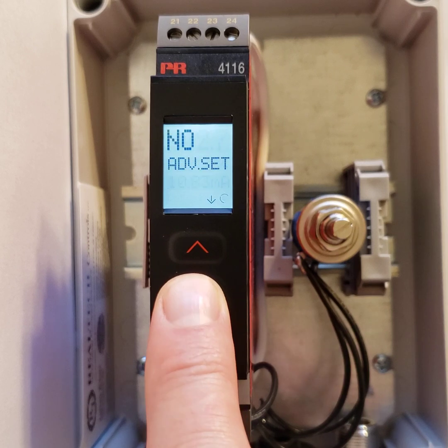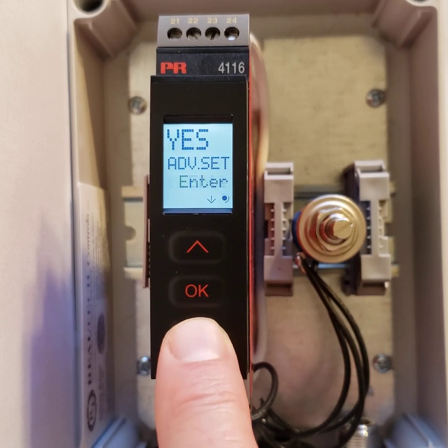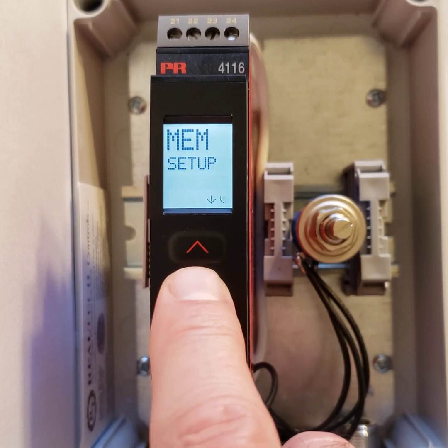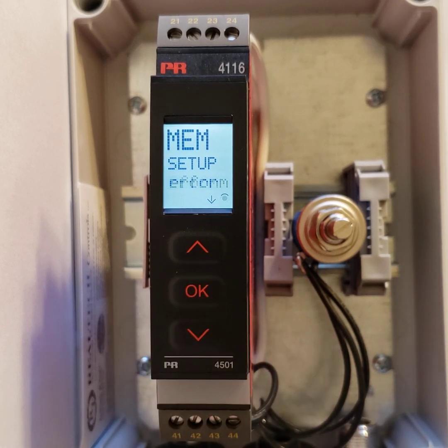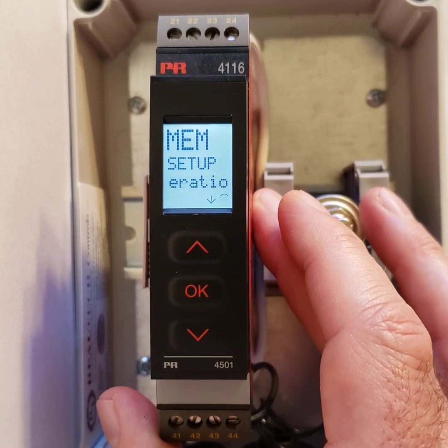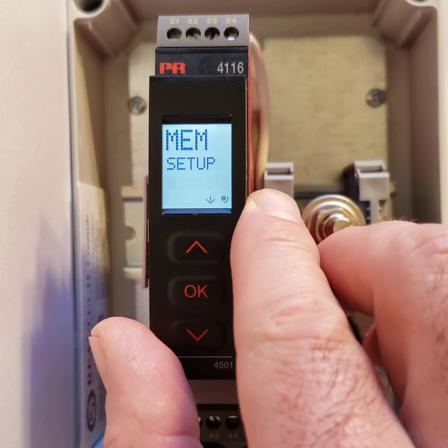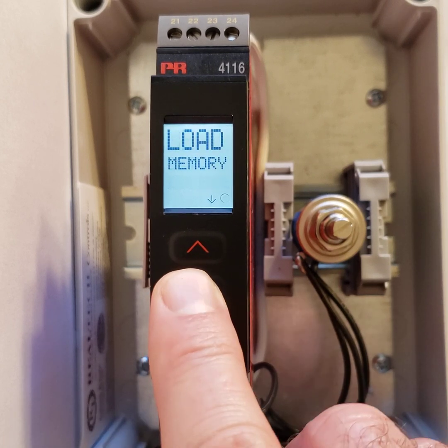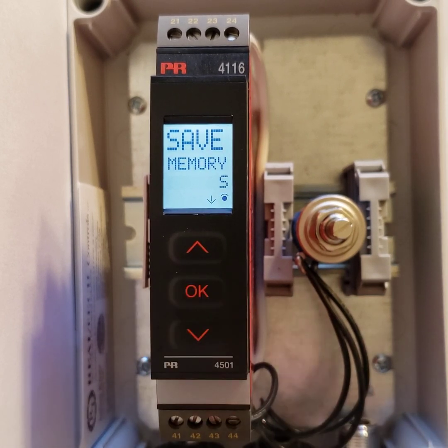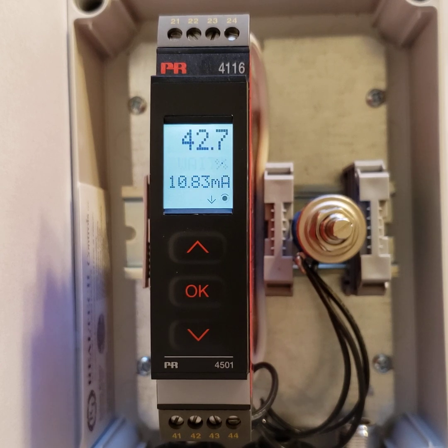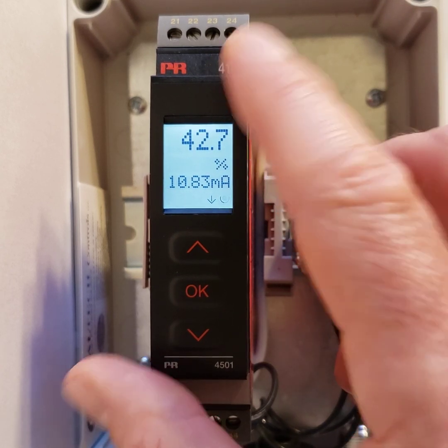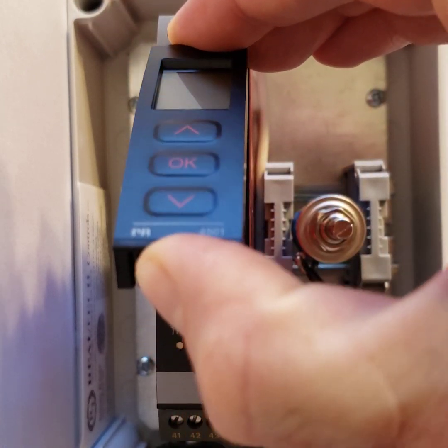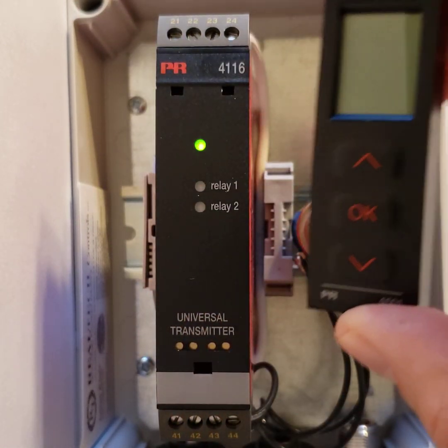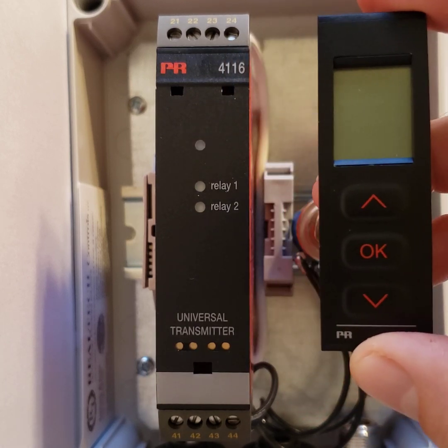To get into the menu, you push OK. You choose Advanced Menu, Yes. The first item is memory, or MEM. What this allows you to do is save your configuration from the 4116 transmitter to the 4501 display. You choose Save. So now my configuration and setup, my relays, my outputs, my inputs is saved to this top display. I disconnect it by pushing my thumb into the clip. And now I can attach this to another transmitter.